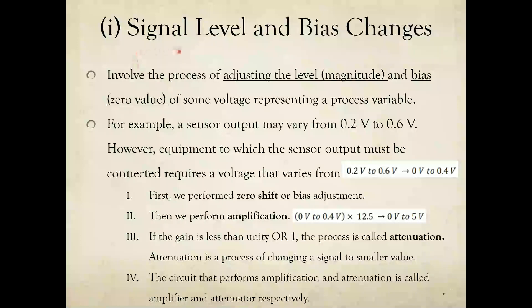The first type of signal conditioning is called signal level and bias changes. These two often work together. It involves adjusting the magnitude of the signal and biasing — meaning the signal should start from zero. For example, a sensor output may vary from 0.2 V to 0.6 V, but the output your system needs is in the range of 0 to 5 V, so you need to convert the signal to that range.